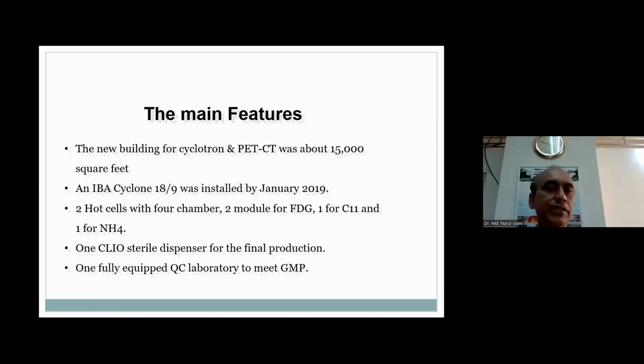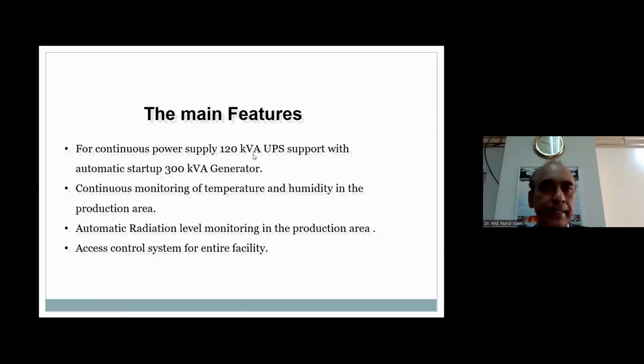Main features of our cyclotron: the new building is about 15,000 square feet, and an IBA Cyclone 18/9 cyclotron was installed in January 2019. It now has 2 hot cells with 4 chambers, 2 modules for FDG, 1 for C11, and 1 for ammonia. There is 1 CLIO sterile dispenser for the final production, and a fully equipped QC laboratory to meet GMP. For continuous power supply, we have 120 kVA UPS support with an automatic startup 300 kVA generator. Continuous monitoring of temperature and humidity is done in the production area. We also have automatic radiation level monitoring in the production area and an access control system for the entire facility.